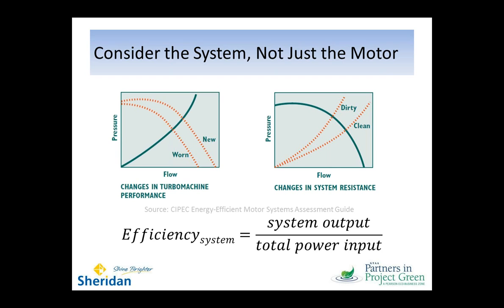Whatever your key system output is, it could be a sustained flow rate you need to have. It could even be, if it's a cooling system, how effectively are we maintaining set point. But take that key system output metric, divide it by the power you're putting into the system to accomplish that work. And so that macroscopic look will allow you to look at all kinds of things in control, in sizing, in maintenance, and see if they've really had an impact in your system.